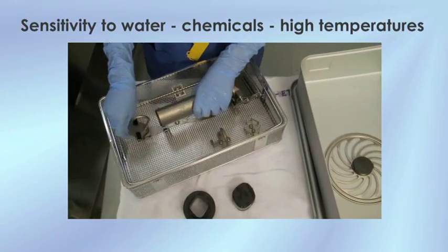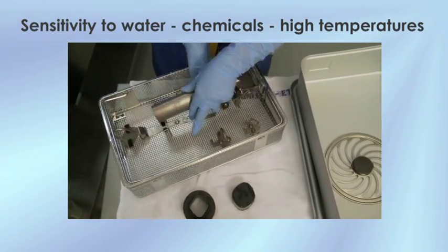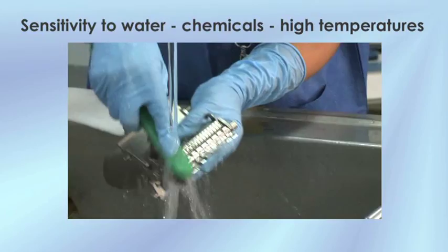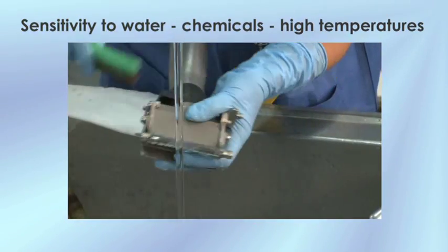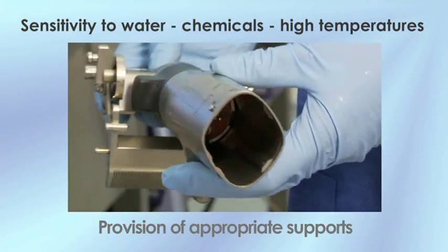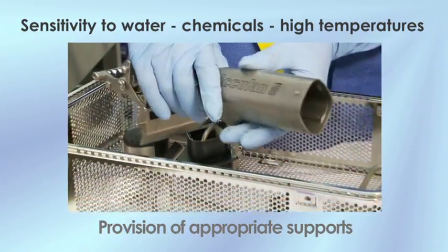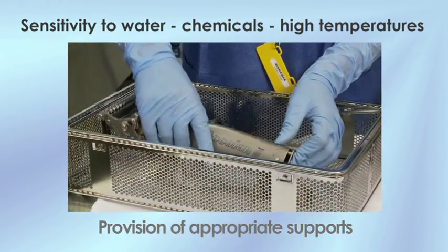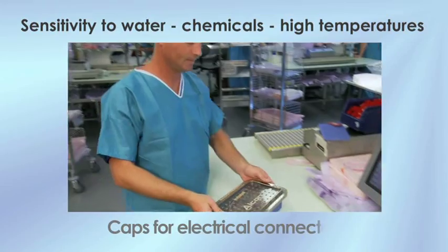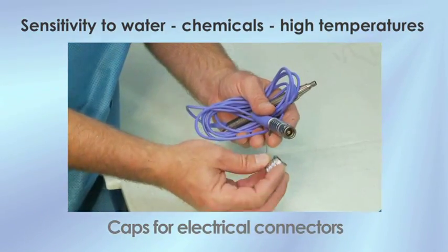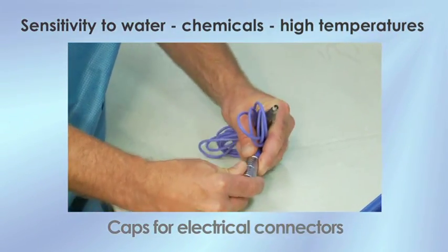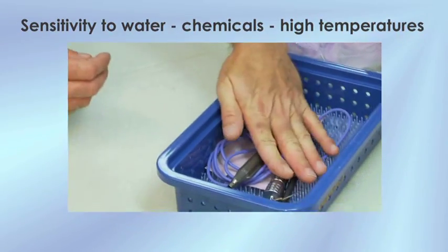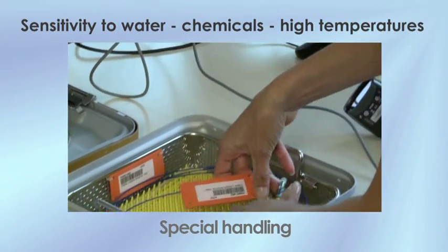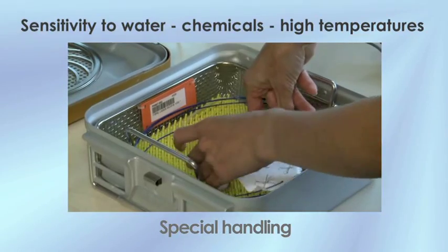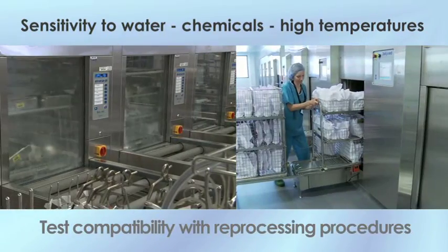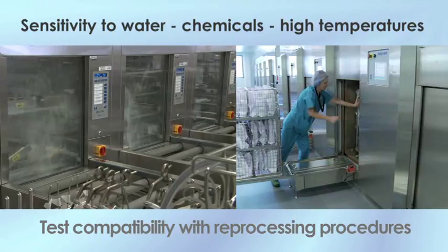To deal with all these constraints, medical device manufacturers should design devices to take account of reprocessing. They should consider providing supports to allow liquid to run off, providing special caps to protect electrical connectors during cleaning and sterilization, and carrying out thorough testing to guarantee that their devices are watertight and compatible with the reprocessing procedures.